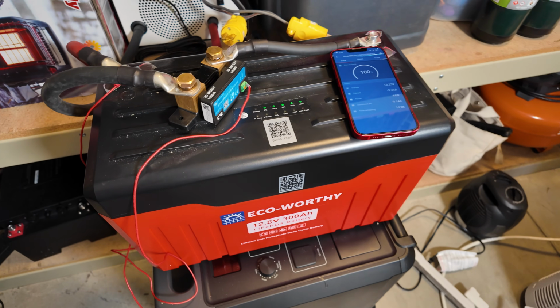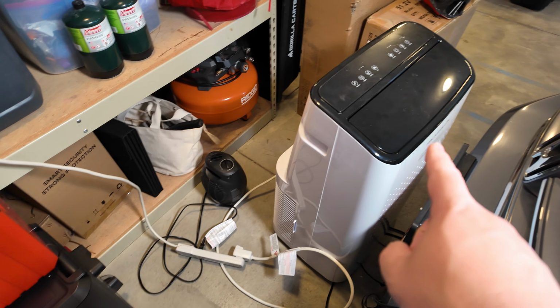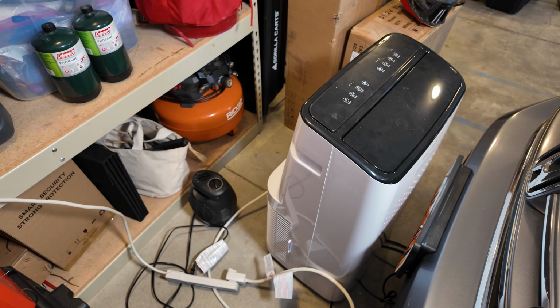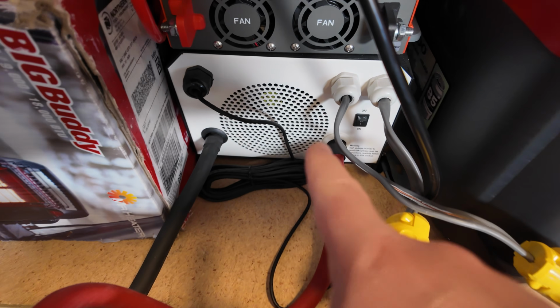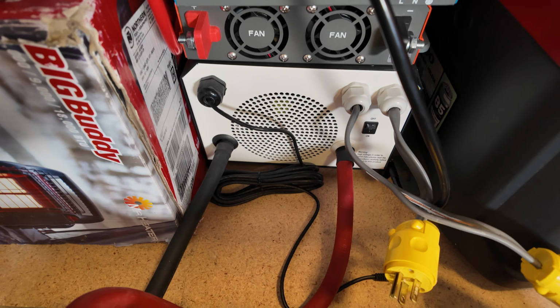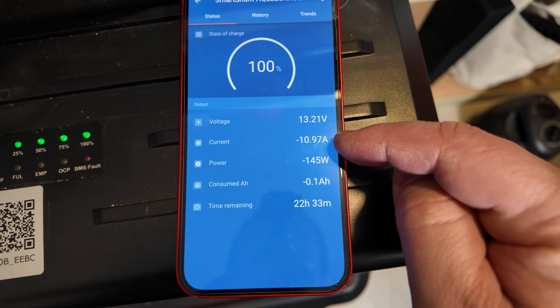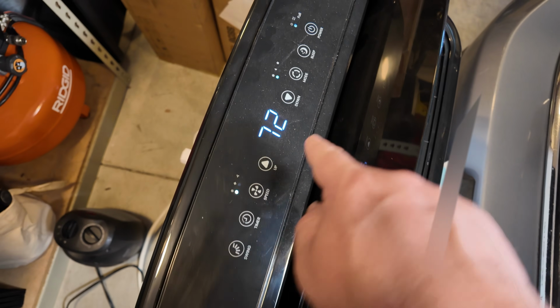All right, next is heavy surge testing. We've got a 15,000 BTU air conditioner here that we're going to use for that. I'm pretty sure this inverter will be able to handle it, it's a low frequency inverter, it handles surges exceptionally well. You can see now we're only pulling about 11 amps, so let's see if it can start it this time.